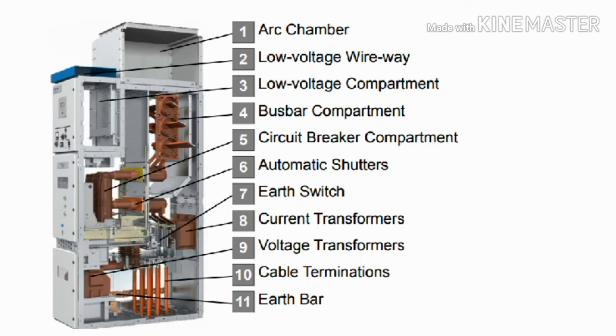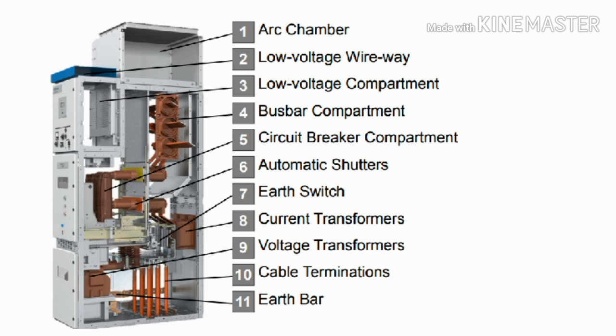Now we will see where these major components are fixed in the switchgear panel. This is the medium voltage switchgear panel. First, at the top side of the panel is the arc chamber — when an arc fault occurs, this arc chamber helps to contain that arc fault. Second, you can see the blue color on the top side, that is the low voltage wireway where low voltage component wires are terminated.